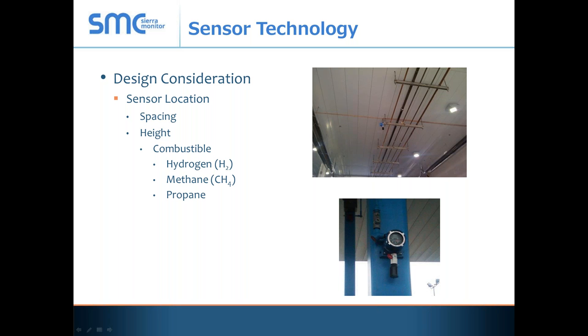For propane, on the other hand, gas detection may be located down low — the lower 18 inches of the garage, or even in pit areas, since propane is heavier than air. For toxics like carbon monoxide and nitrogen dioxide, we place sensors in the breathe zone. And finally, the one thing we always stress is using common sense for the location — just like we mentioned before, where are you fueling, what are you doing, where are you working on the vehicle?